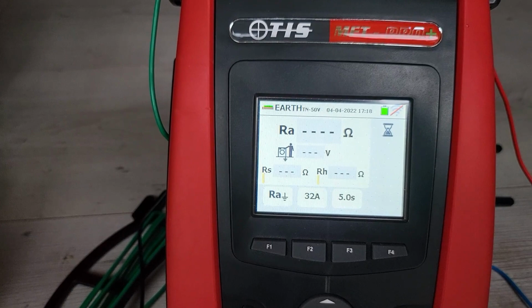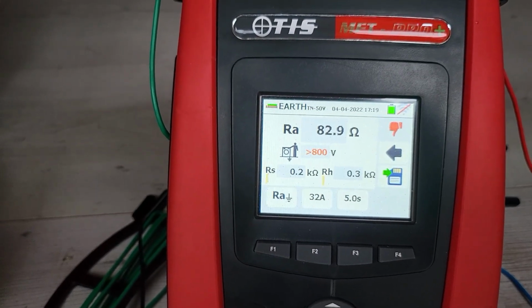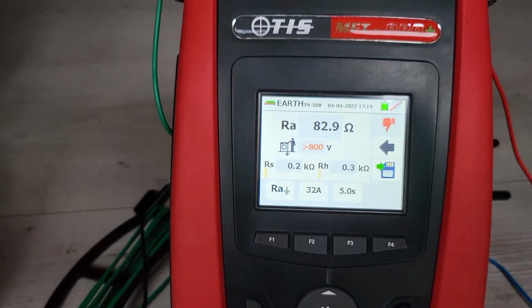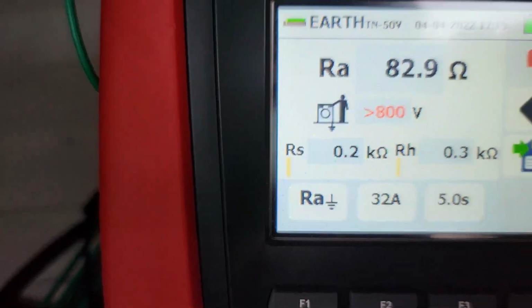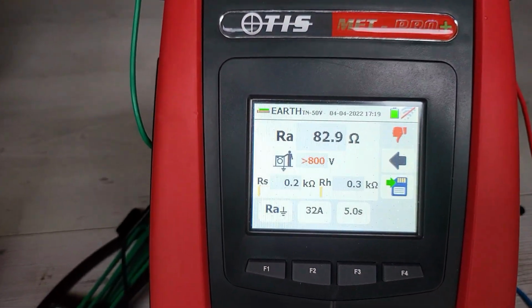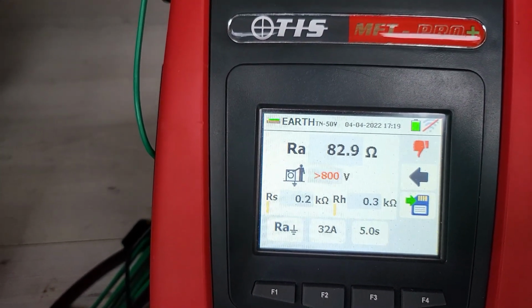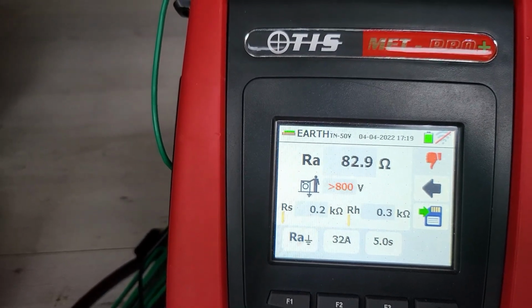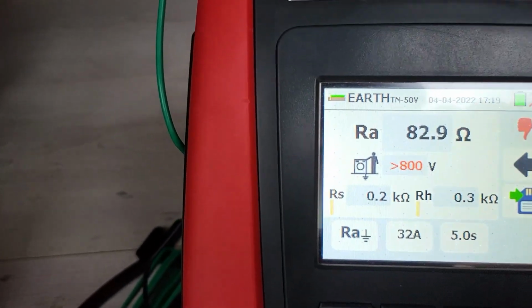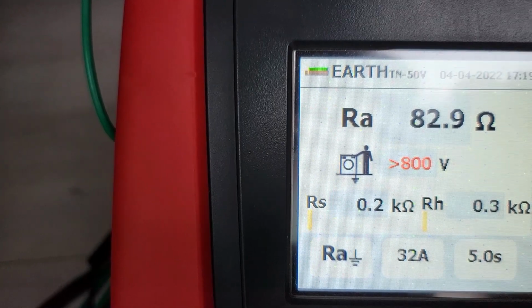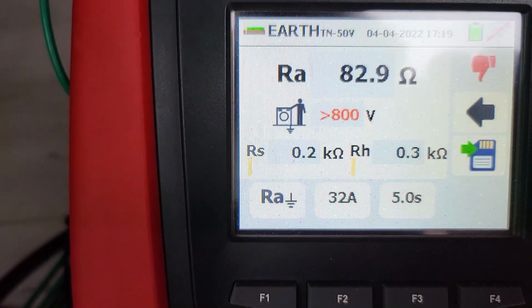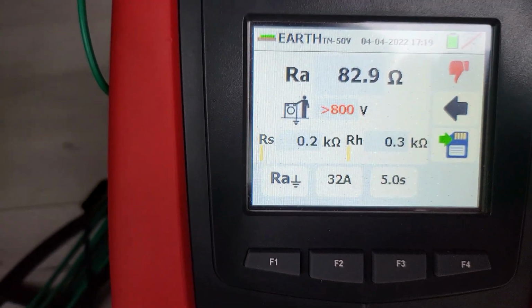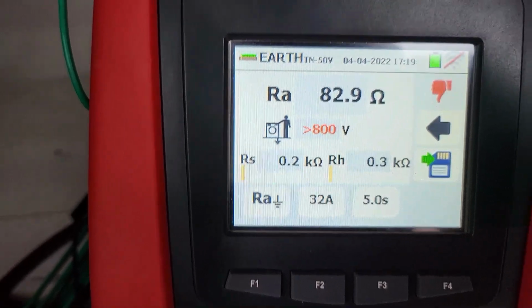So this is something it doesn't rush at, none of the test sets do. You can see it's given me a fail because I've got this set for as if it was a 32 amp circuit, which it isn't. And you can see here we've got 82.9 ohms on the RA, and you can see your RS and RH values there as well. So got 0.2k and 0.3k.